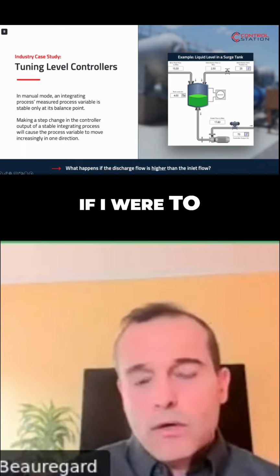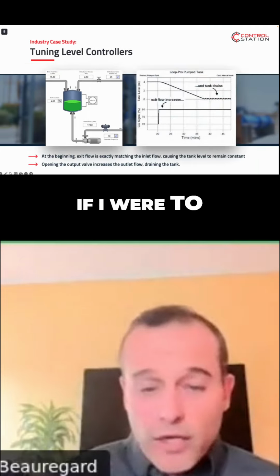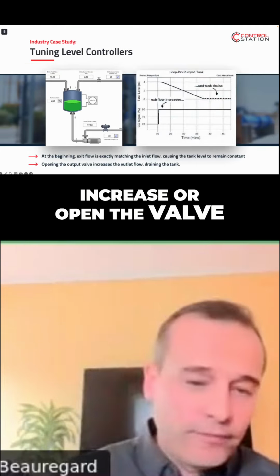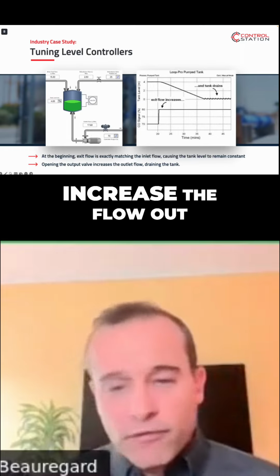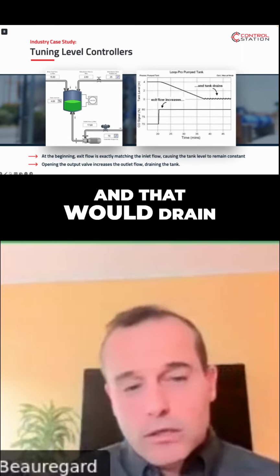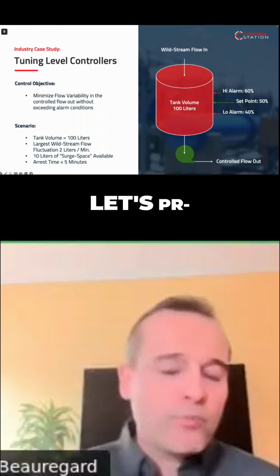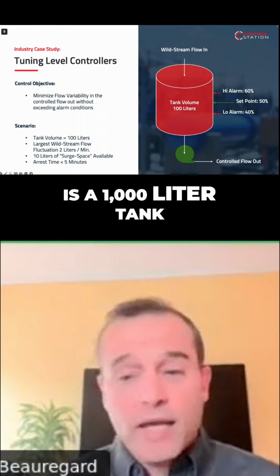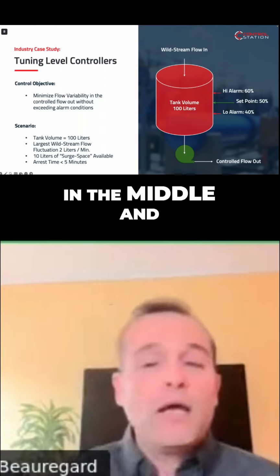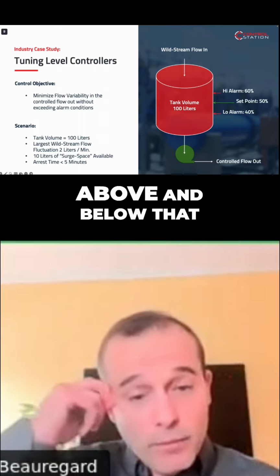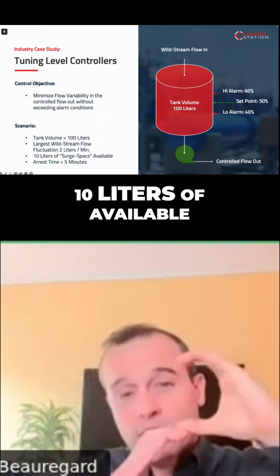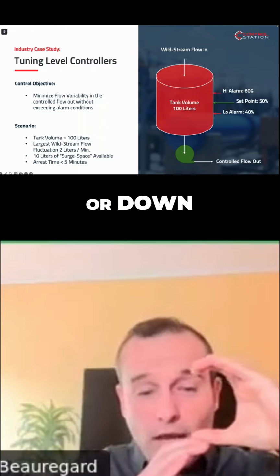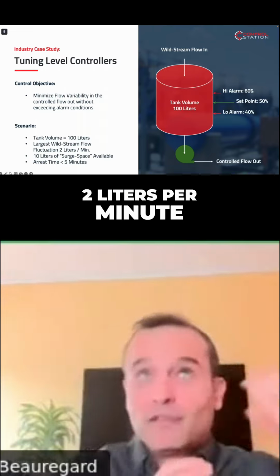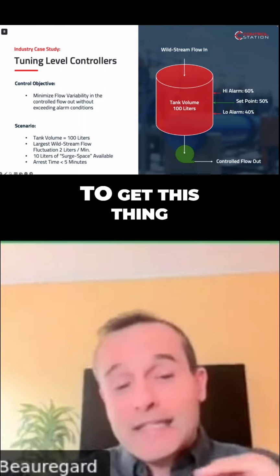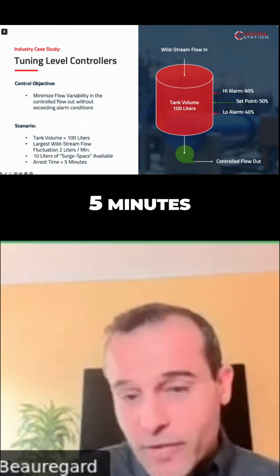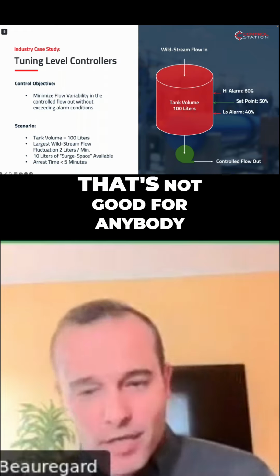So if I were to increase or open the valve, that would increase the flow out of the tank, and that would drain the tank completely. Let's assume that this tank is a 100-liter tank, that we generally stay in the middle, and then we have alarms 10% above and below that. That means we have 10 liters of available space to go up or down, and we know that our fluctuations can be 2 liters per minute. 10 divided by 2 means that we've got to get this thing around in less than 5 minutes, or we're going to get an alarm, and that's not good for anybody.